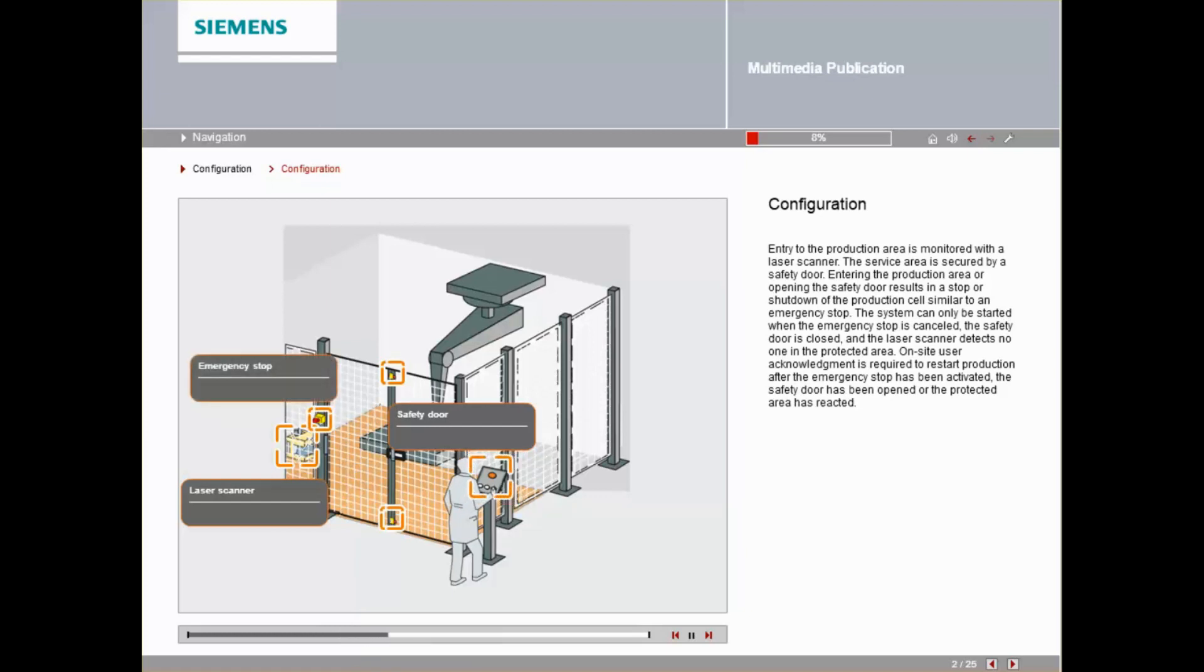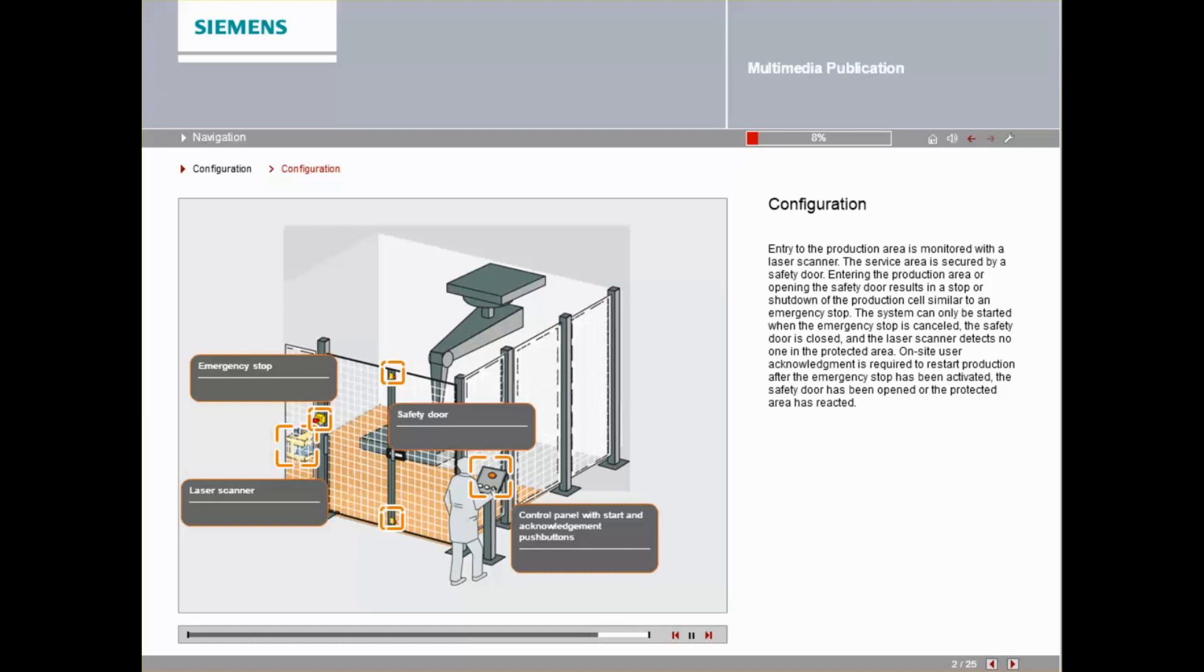The system can only be started when the emergency stop is cancelled, the safety door is closed, and the laser scanner detects no one in the protected area. On-site user acknowledgement is required to restart production after the emergency stop has been activated, the safety door has been opened, or the protected area has reacted.